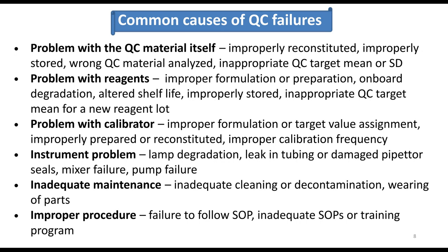QC failure can represent a problem with the reagent, so improper reagent formulation or preparation, onboard degradation of the reagent, which is actually a very common cause for QC failure, altered shelf life for a new lot, for example, reagents that are improperly stored, or reagents that have inappropriate QC target means for a new reagent lot.